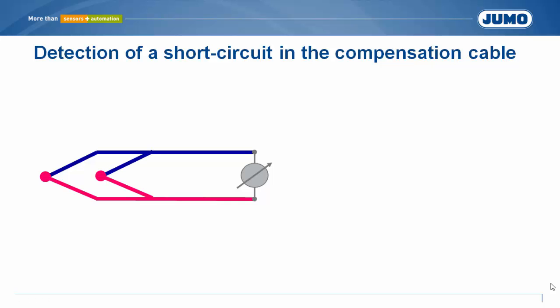In the event of a short circuit in the compensation cable, a second thermocouple is produced. The parallel connection of the two elements results in a temperature which lies between the measuring temperature and the temperature at the short circuit point. The short circuit cannot be detected.